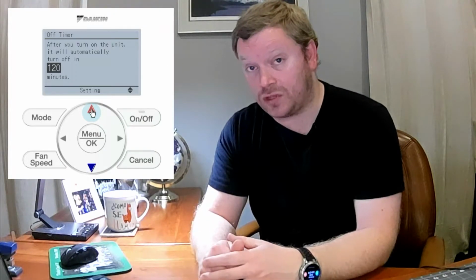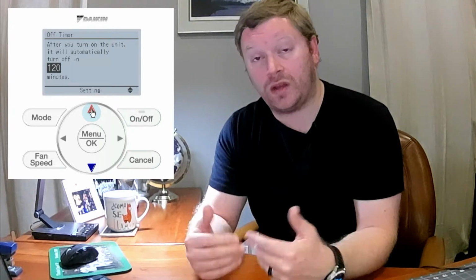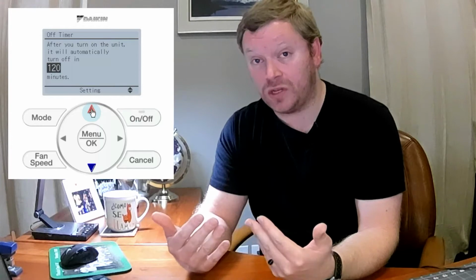Let's say heat set to 70 for that allotted time of 2 hours, and then it will automatically shut off. You then would have to manually turn it back on or have the schedule turn it on at a certain time period, at which point it would run for 2 hours and then automatically shut off. The reason I don't recommend or prefer, in my opinion, to use the off timer is because the inverter heat pump systems are designed to be on, maintaining space temperature all the time. I don't want mine turning off.